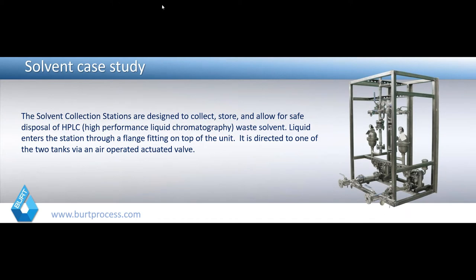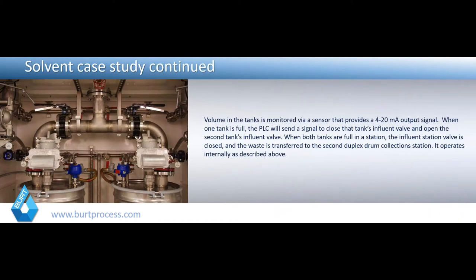Here's a quick example of how systems go together — a solvent collection station designed to transfer waste solvent from high-performance liquid chromatography units. You have a solvent collection pit, a solvent collection transfer system located adjacent to the pit, stainless steel with different air valve fittings and pulsation dampers. These transfer into a drum-based collection system with shutoff valves to fill one drum then the other, conservation vents, level instrumentation, and a fire suppression system.